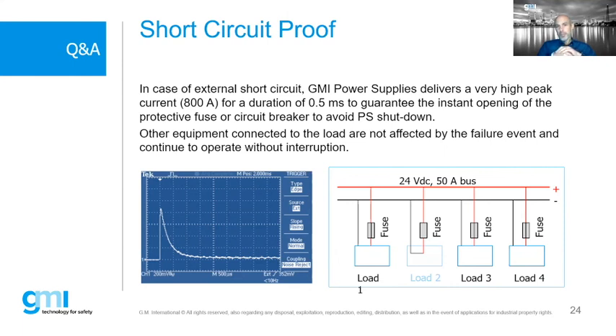But we developed a special feature on our power supplies. In case of short circuit, GMI power supplies deliver and generate a high peak of current, 800 amps. We are talking about very high current for a small duration, 0.5 milliseconds, in order to open completely and blow the fuse or the circuit breaker, to avoid the power supply shutdown. So the other loads connected to the power supply will continue working without any problem. This is a special feature that was developed in cooperation with the customer that required it.